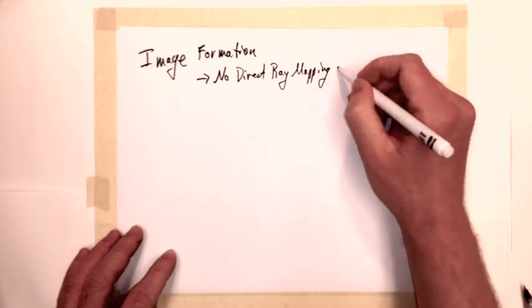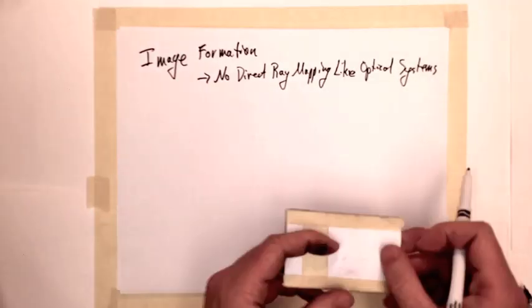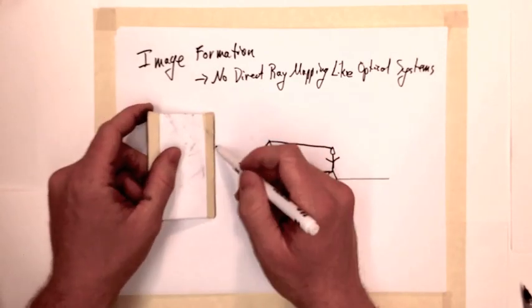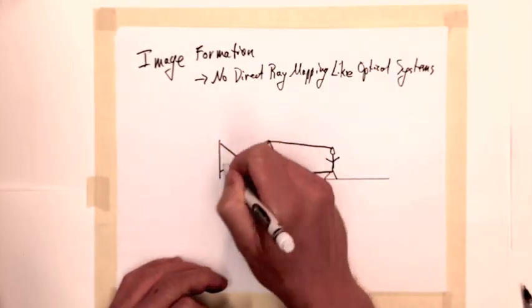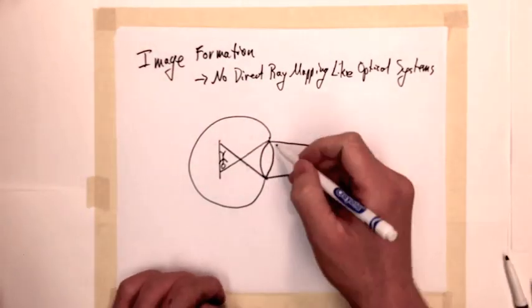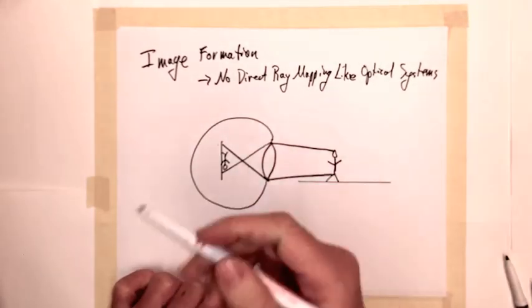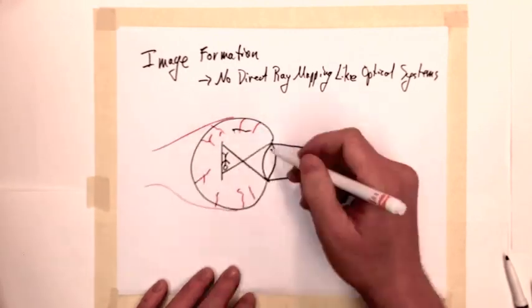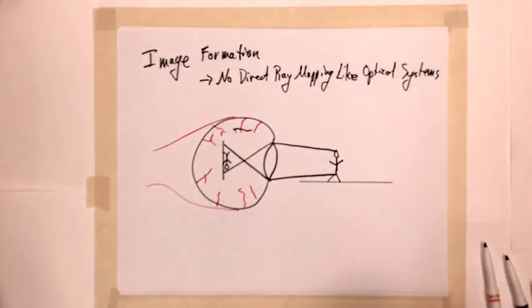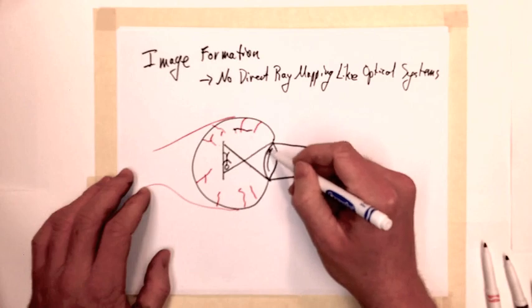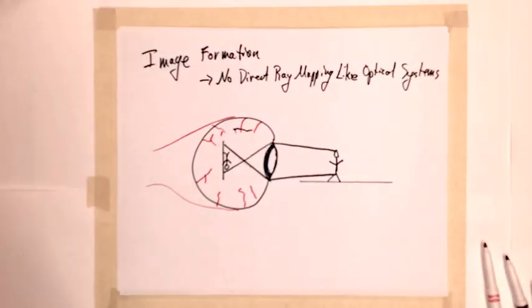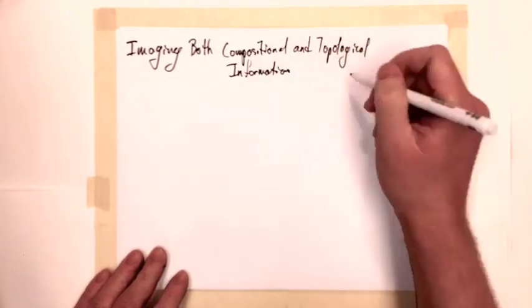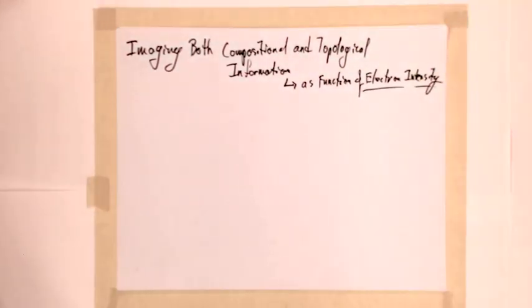In the SEM, the final signal used for image formation is a collection of electrons from any one or more of the scattering processes that can take place. In the most common methods of BSE detection, there is no direct ray path from the sample to the image as in optical imaging. In some cases, we collect the electrons as electrical information and in others as optical information. This data is used in coordination with the scan speed and location to reconstruct an image of the sample. Only in the diffraction patterning scheme do we see a direct ray path from sample to image.